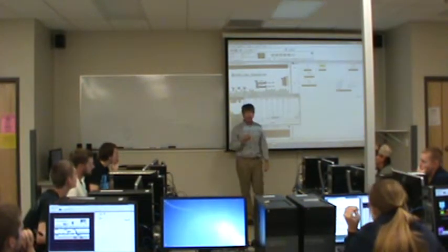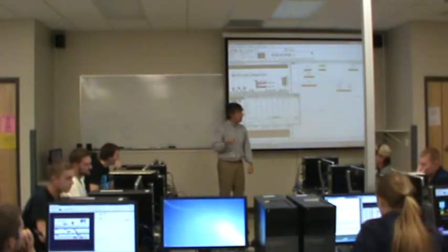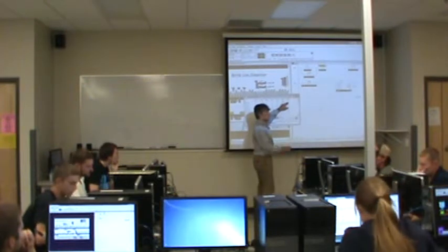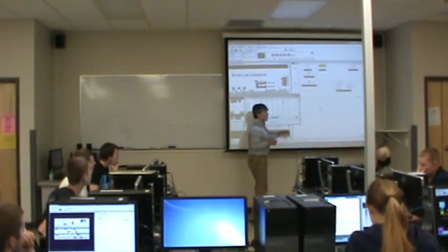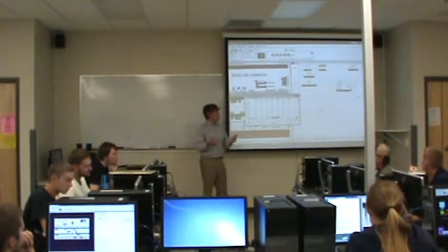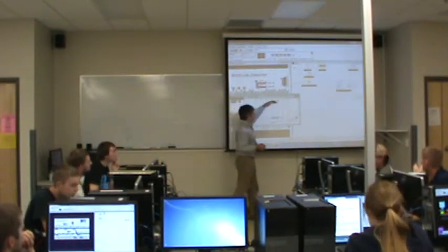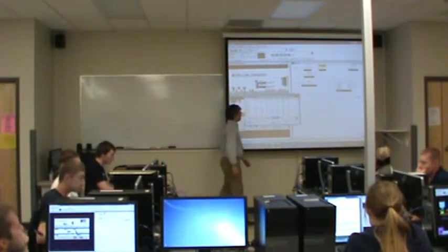Remember we shut off the program and yet remembered how many times we hit the button? That's because it has a whole word of data that's dedicated to storing that information. Okay? And that information in memory is not cleared when the program stops. That's why when it comes back on, the instructions are still referencing the same memory location. So there's still an accumulated value in that counter.